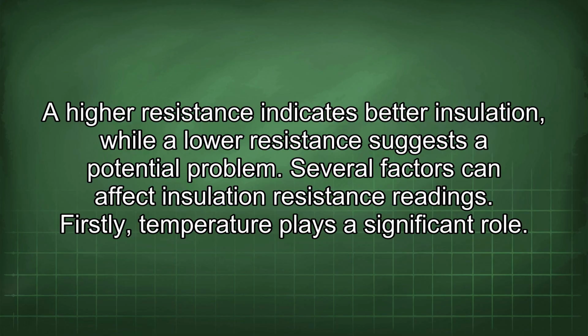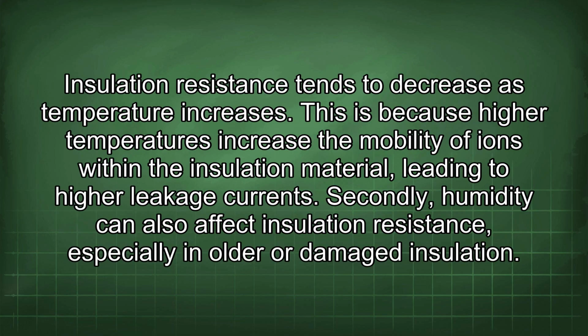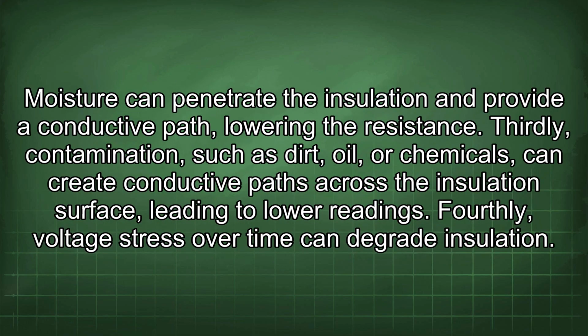Several factors can affect insulation resistance readings. Firstly, temperature plays a significant role. Insulation resistance tends to decrease as temperature increases. This is because higher temperatures increase the mobility of ions within the insulation material, leading to higher leakage currents. Secondly, humidity can also affect insulation resistance, especially in older or damaged insulation. Moisture can penetrate the insulation and provide a conductive path, lowering the resistance. Thirdly, contamination, such as dirt, oil, or chemicals, can create conductive paths across the insulation surface, leading to lower readings.